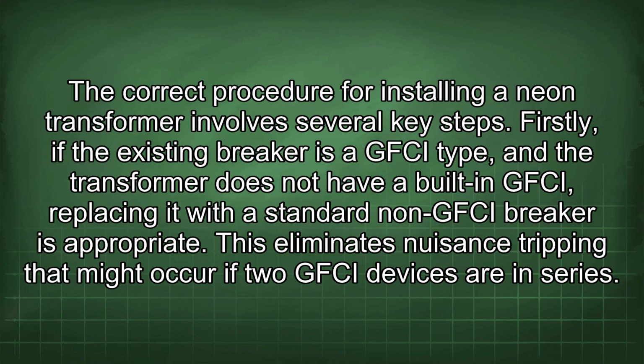The correct procedure for installing a neon transformer involves several key steps. Firstly, if the existing breaker is a GFCI type and the transformer does not have a built-in GFCI, replacing it with a standard non-GFCI breaker is appropriate. This eliminates nuisance tripping that might occur if two GFCI devices are in series.